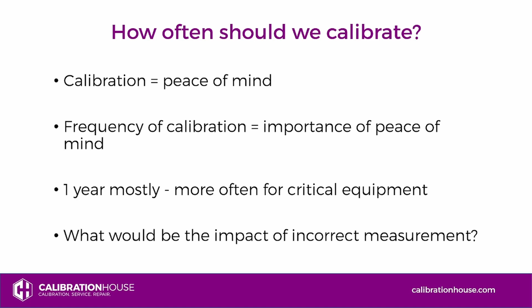Next, we'll look at the practicalities of calibration. Often the unit that needs to be calibrated is crucial to an organization's processes, its measurements, its checks, and they can't bear to be without it. They don't have a spare unit, and they can't afford for it to be away for weeks at a time. Here at Calibration House, if a unit must come off site, then we have a 5 working day turnaround time. We perform the calibrations in our state-of-the-art laboratory in Durham that was renovated in early 2022.